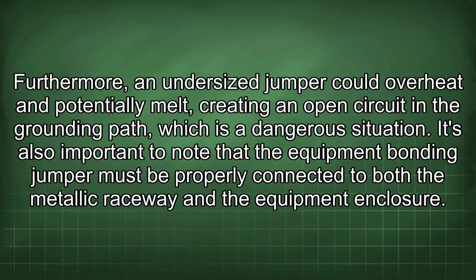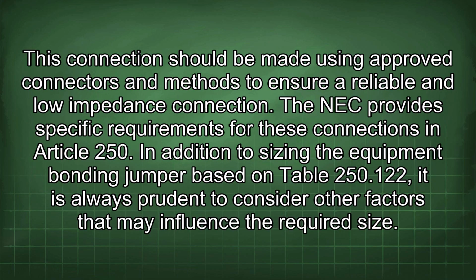Furthermore, an undersized jumper could overheat and potentially melt, creating an open circuit in the grounding path, which is a dangerous situation. It's also important to note that the equipment bonding jumper must be properly connected to both the metallic raceway and the equipment enclosure. This connection should be made using approved connectors and methods to ensure a reliable and low impedance connection. The NEC provides specific requirements for these connections in Article 250.